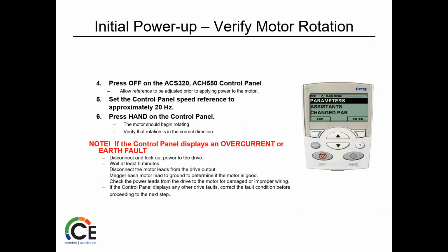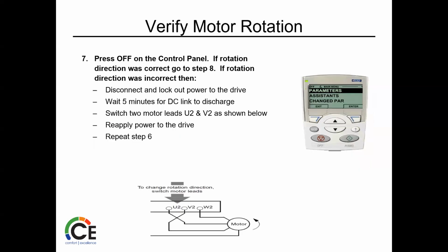But again, there are some safeties in there, it verifies motor operation, and it does a lot of this as it's testing. But if you want to make sure and you're just starting it up, hit hand on this thing, check and make sure it's running the right way. And of course, press off because we don't want to leave it in hand.